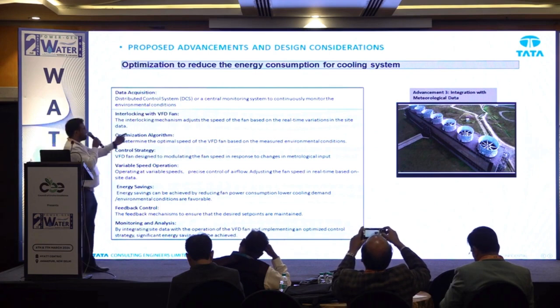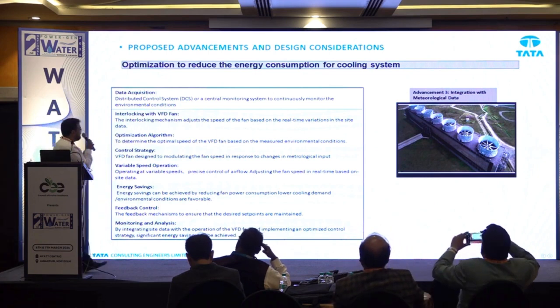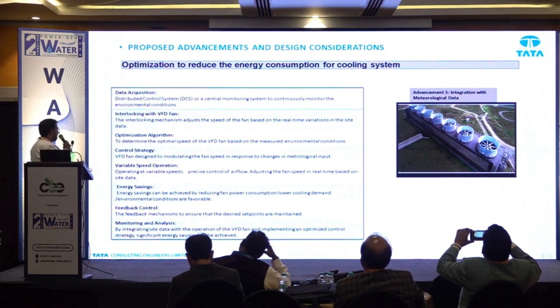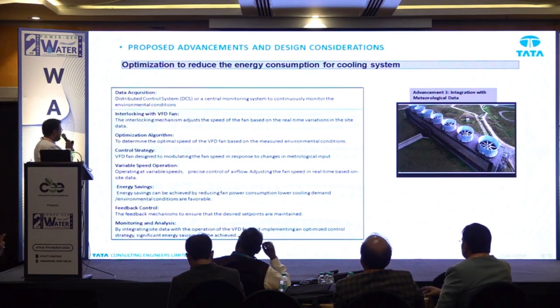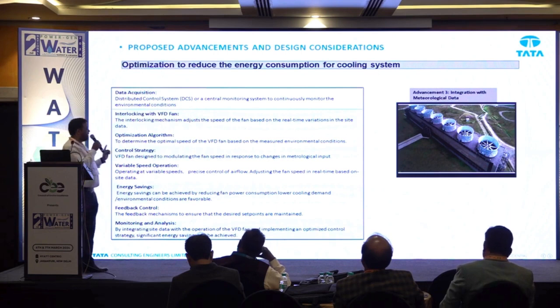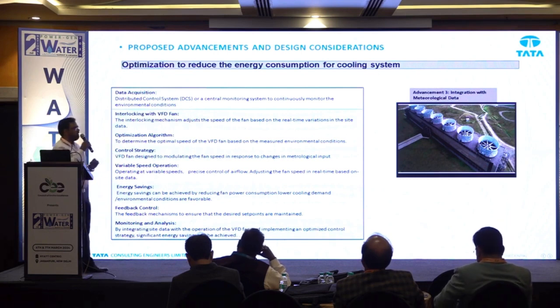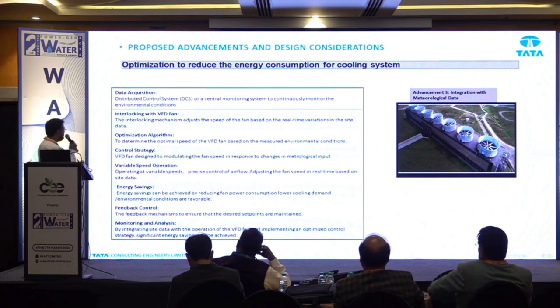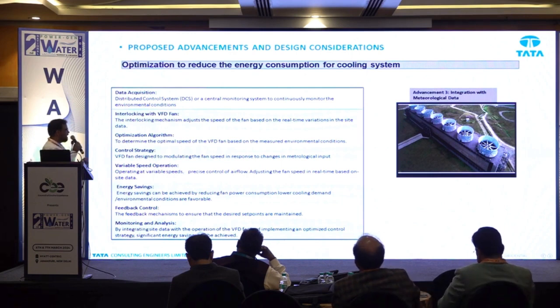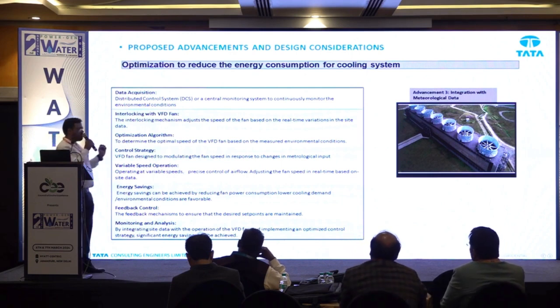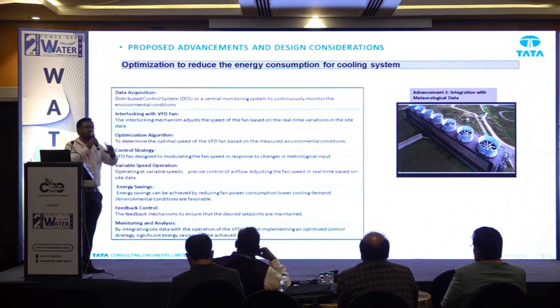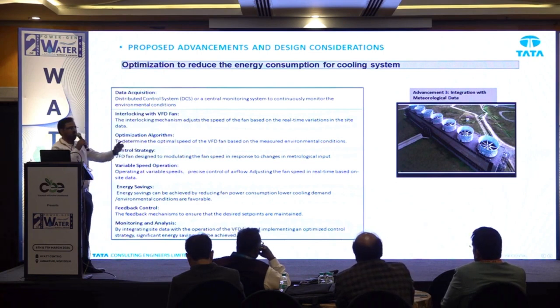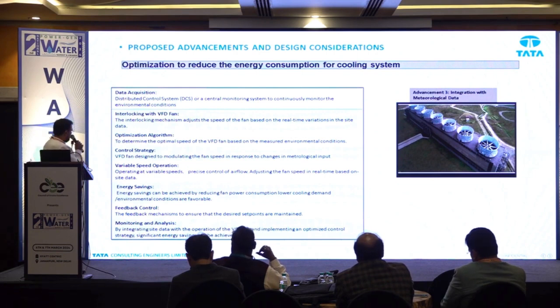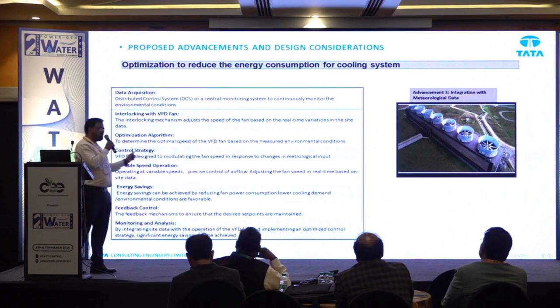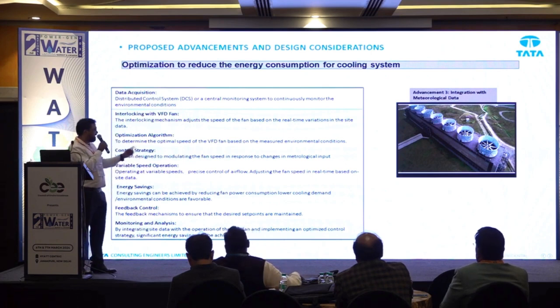So in this third advancement, interlocking with the VFD fan, the interlocking mechanism adjusts the speed of the fan based on real-time variation in the site data. Second, an optimization algorithm determines the optimal speed of the VFD fan based on the measured environmental condition. Third is control strategy - the VFD fan is designed to modulate the fan speed in response to changes in meteorological data: wet bulb, dry bulb, and relative humidity.